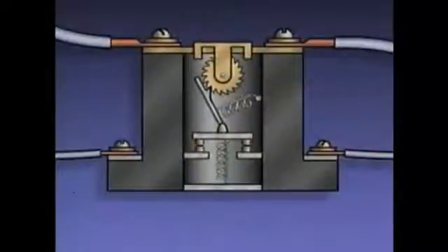Now let's look at the entire solder pot. From this angle, we can see the top of the ratchet wheel here. We can also see that the solder pot has a mechanical linkage, movable contacts, which are in the motor controller's control circuit, and 2 springs. The ratchet wheel, which is set on the rod, holds the mechanical linkage in place.